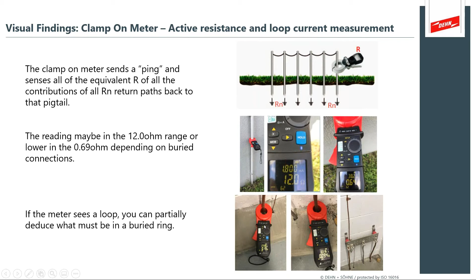So here I've got an example where I measured a very low value of 0.062 around the structure. And I knew I was looking for a buried ring, but I found a 19 ohm pigtail. 19 ohms will tell me that that pigtail is not like the rest. And I can deduce that I had a problem with the buried ring. The customer had to excavate and repair a buried connection. And this is important to understand. What do you expect to see? What do the rest of the measurements look like? And then it allows you to evaluate the difference.